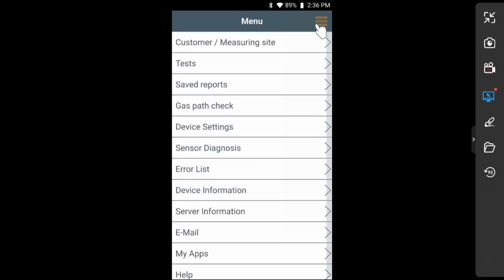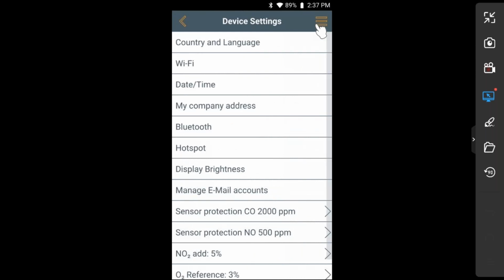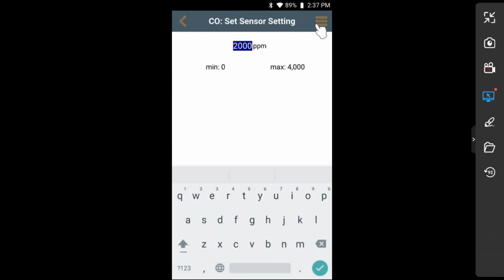And like I said, it's right under the main menu: path gas path check, device settings. It just gives you your device settings, what you can do to the display itself, add Bluetooth, delete the Bluetooth, email information. One thing that's important that I always recommend customers do is look at the sensor protection, carbon monoxide. If I click on that, I can protect the CO cell.